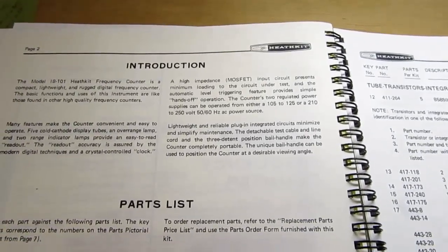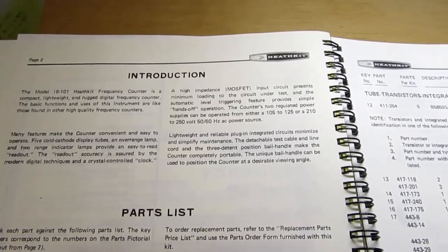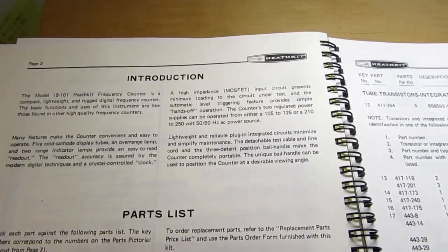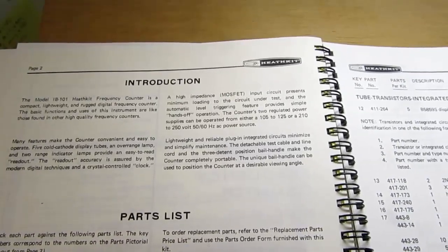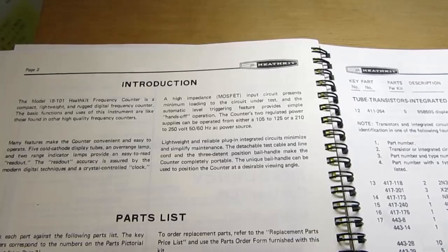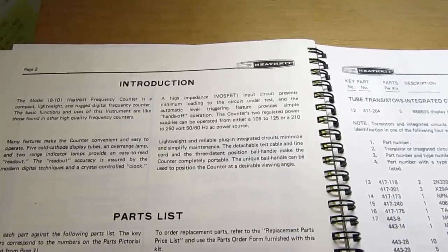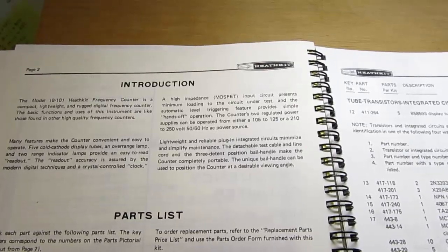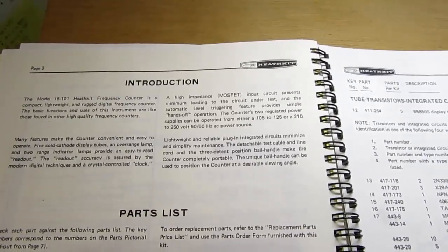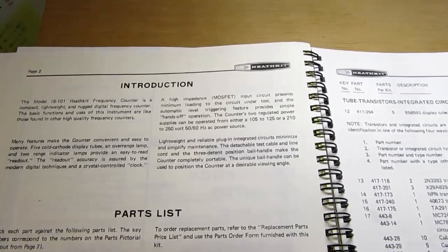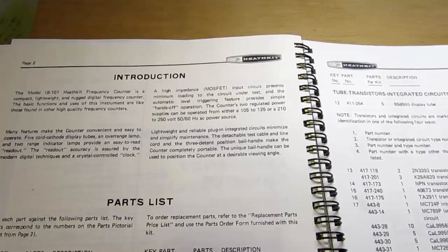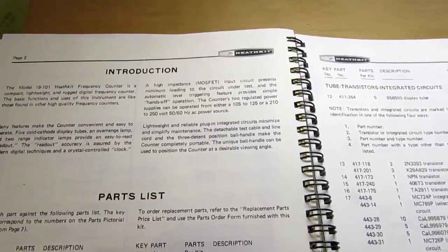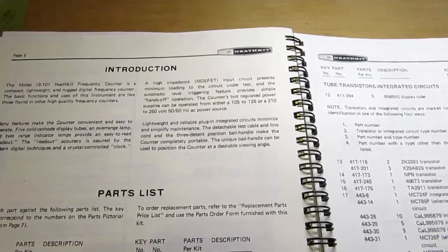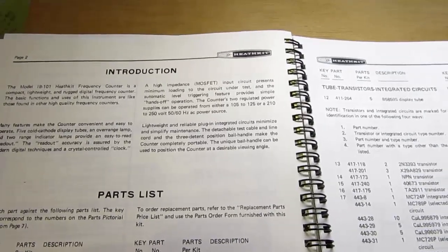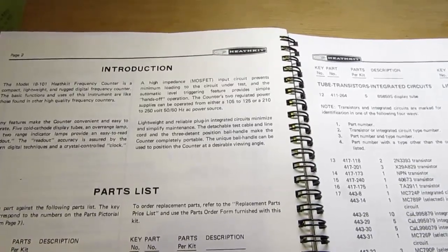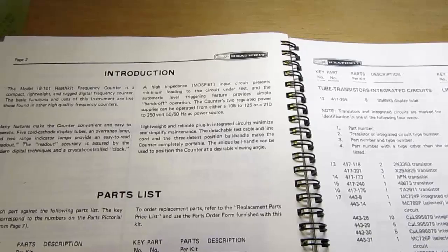The readout accuracy is assured by modern digital techniques and a crystal-controlled clock. The high-impedance MOSFET input circuit presents minimum loading to the circuit under test, and the automatic level triggering feature provides simple hands-off operation. The counter's 2 regulated power supplies can operate from either a 105 to 125 or a 210 to 250 volt, 50-60 Hertz AC power source. Lightweight and reliable plug-in integrated circuits minimize and simplify maintenance. The detachable test cable and line cord and the 3 detent position bail-like handle make the counter completely portable. The unique bail handle can be used to position the counter at a desirable viewing angle.